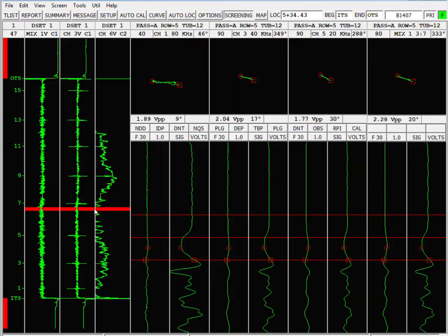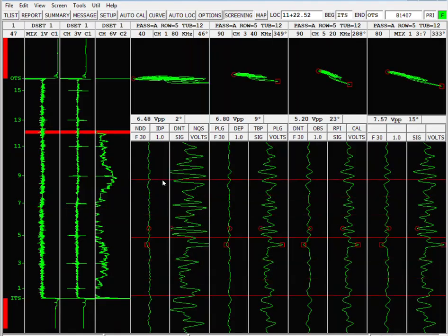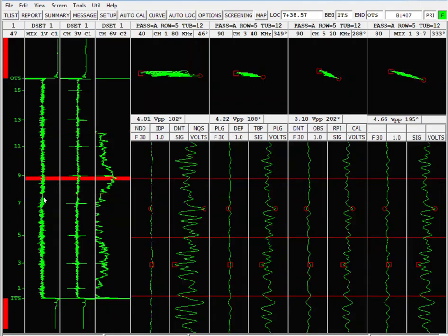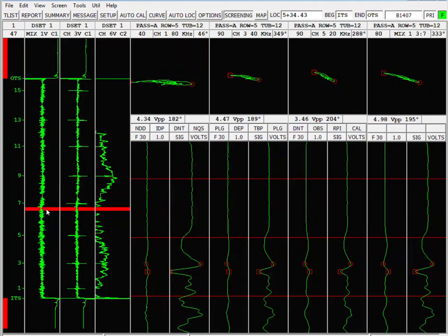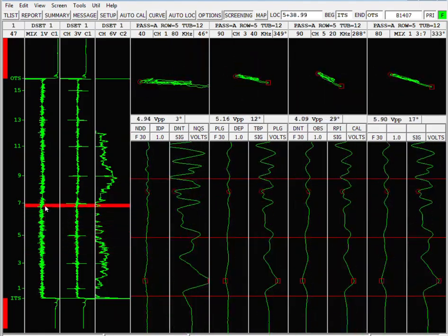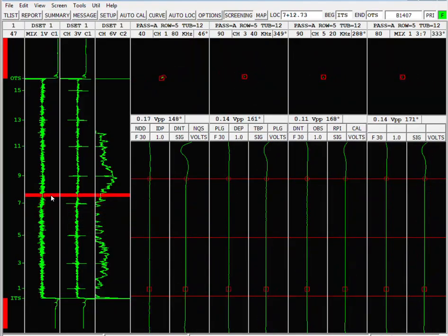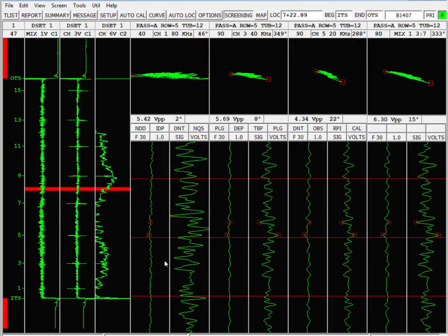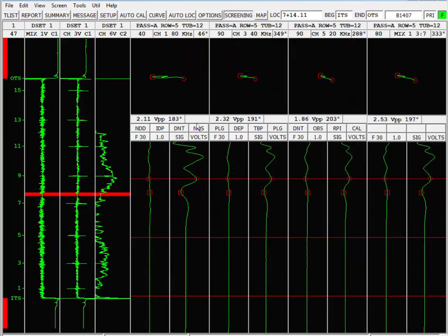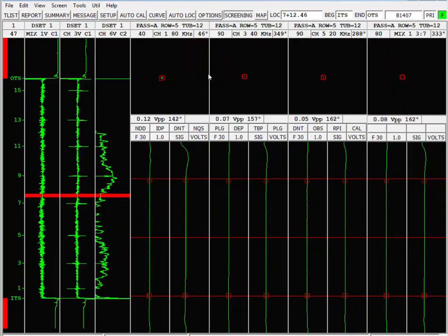Now here, I can look at the strip charts and easily pick out, because I have a trained eye to spot bad data. Look at the strip chart right about here. See how you got all this fuzz going on down the length of the strip chart? That's normal tube data. You've seen a bunch of probe wobble, there's probably a bunch of scale in there. But when you get to this particular spot, you can look at the expanded strip charts and see it's just dead. But when the probe stops moving because the operator quit pulling on the probe, you get a dead spot.